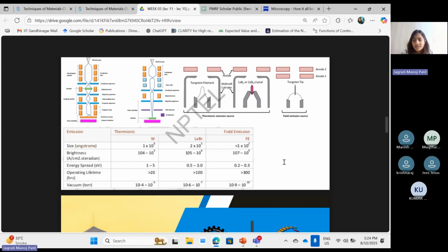Yeah, nowadays all systems are field emission. You won't find that many systems with thermionic emission. Is there any advantage, or is it only the commercial factor, I mean the price factor? Yes, exactly, only the price factor. And these systems also don't require that high maintenance. Of course, they are high maintenance systems, but with respect to each other, field emission systems are much easier to maintain.